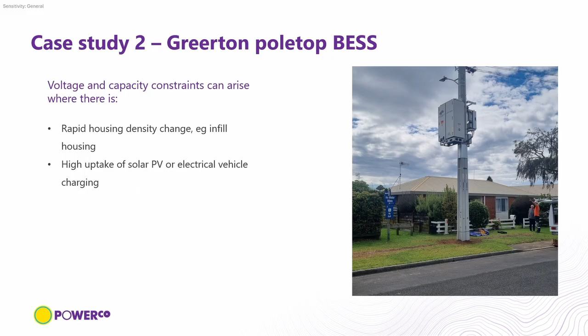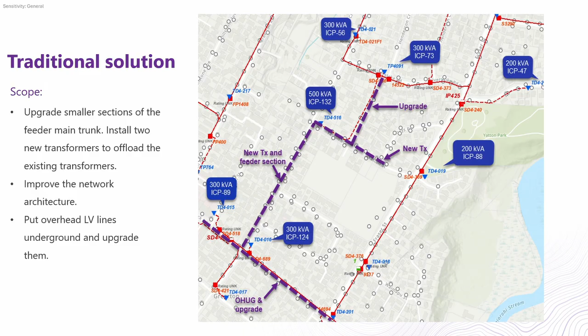The usual solution is to upgrade the network — increase the cable size or overhead conductor size, put new transformers in. They're 250 kVA at the moment; we would put 300 kVA transformers in. Naturally it costs a fair bit of money and takes time to implement, especially with long lead time items.